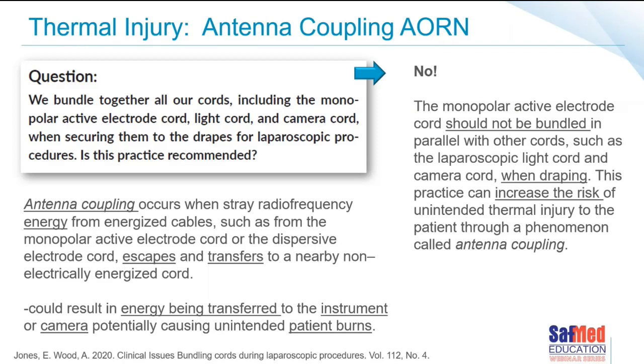The reason for that is that you have an increased risk of unintended thermal injury from a phenomenon known as antenna coupling. So, a new word for me. This phenomenon, antenna coupling, occurs when there's a stray bit of energy from an energized cable, like the monopolar active electrode, i.e. the diathermy, that can escape and transfer to a non-energized cord. And that in turn can result in injury both to the patient and of course to your equipment that is potentially right next to it. So very important not to bundle everything together.